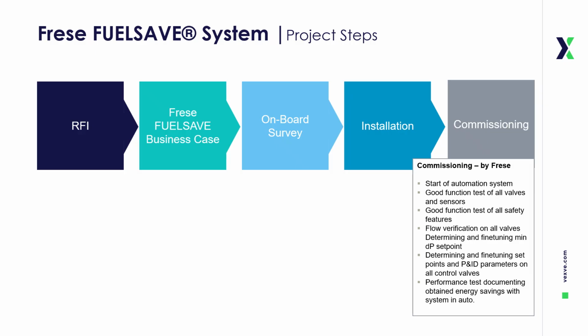Step 5 is commissioning, conducted by Frese. This phase begins with the startup of the automation system, followed by thorough function tests on all valves, sensors, and safety features. Flow verification is carried out across every valve to ensure proper operation. Next, minimum differential pressure set points are determined and fine-tuned, along with the control and P&ID parameters for each control valve. Finally, a full performance test is conducted. This documents the energy savings achieved with the system running in automatic mode. The commissioning stage confirms that the FuelSave system is fully optimized, safe, and ready to deliver measurable efficiency improvements.